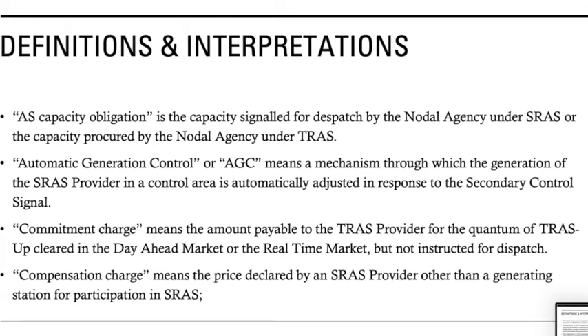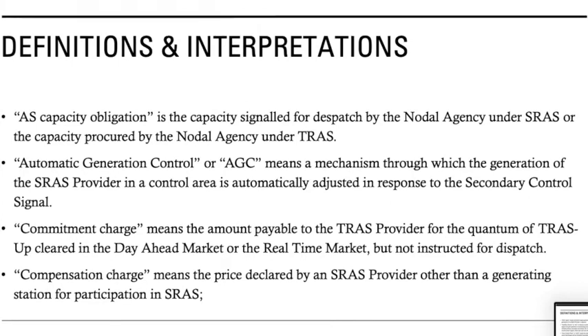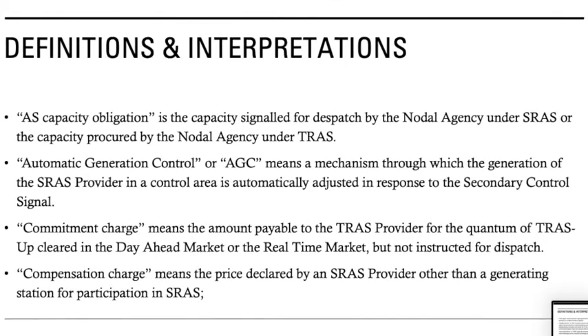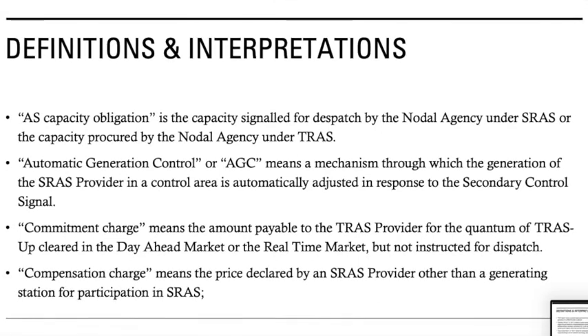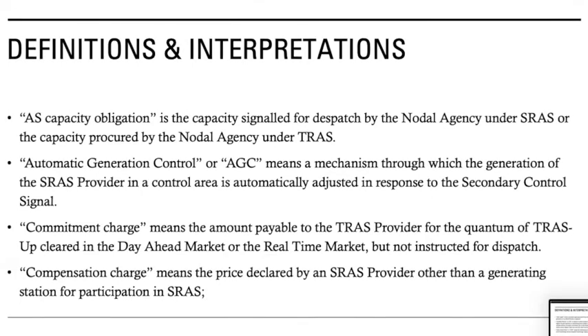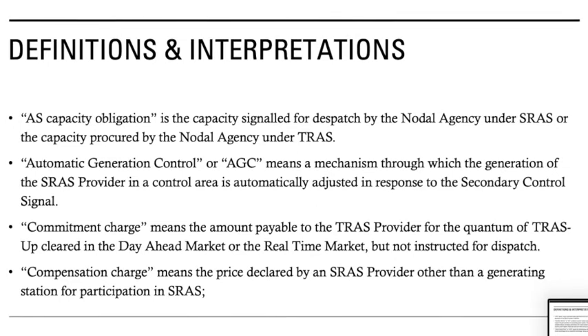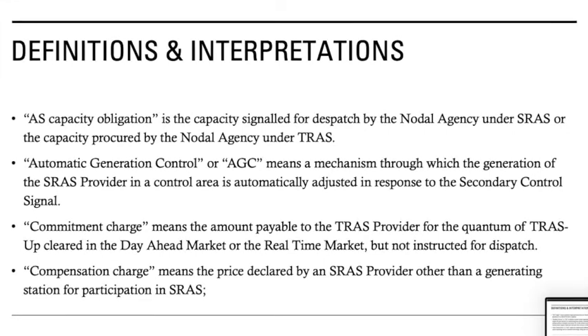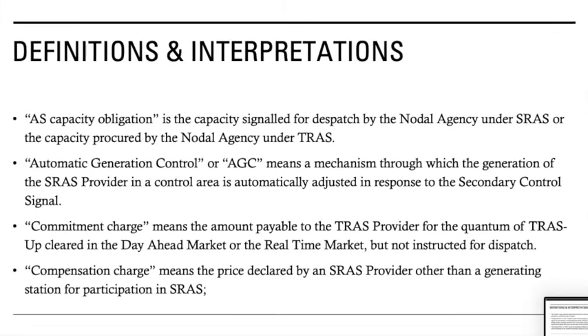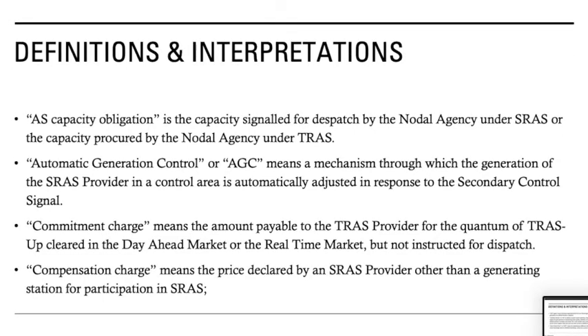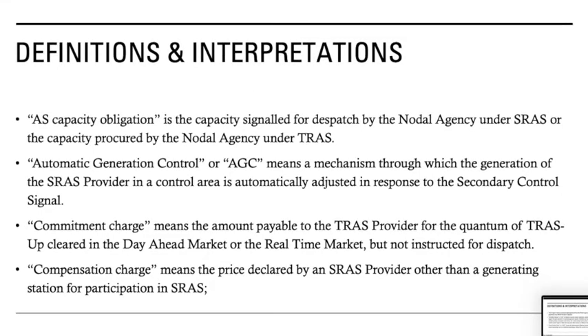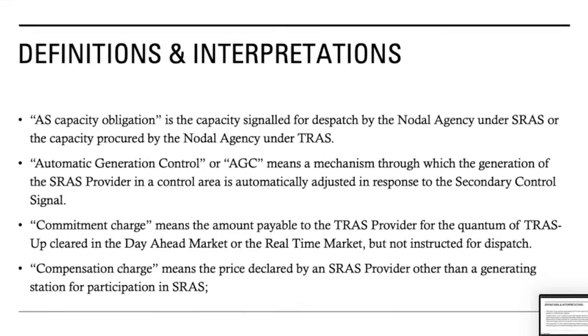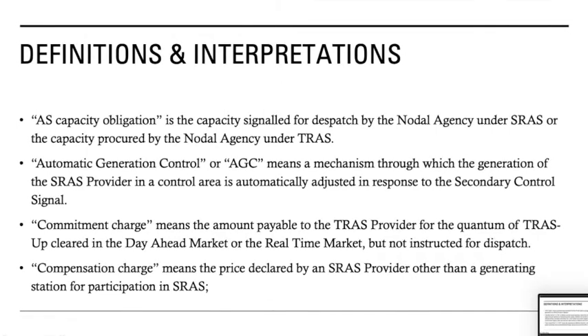Coming to the next term — Automatic Generation Control or AGC — which is basically a mechanism through which the generation of the SRAS Provider in a control area is automatically adjusted in response to the secondary control signal. For example, for a 660 MW plant, suppose a limit of 35 MW is provided. Based on the unit size, a plus or minus signal is generated — that is the maximum change which the grid can do in the unit's load set point. That change is basically called an AGC, meaning the generation control system is automatically in the hand of the grid.